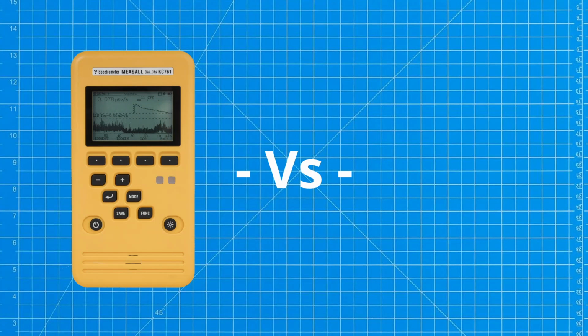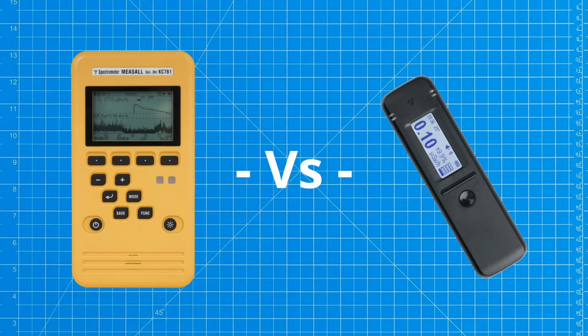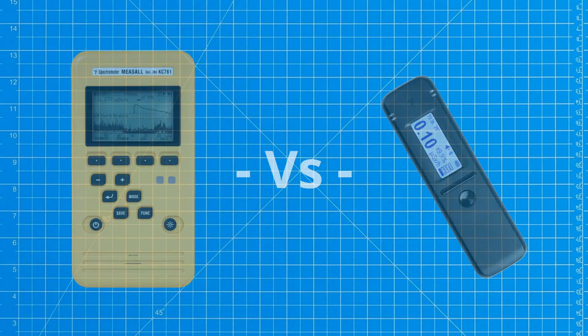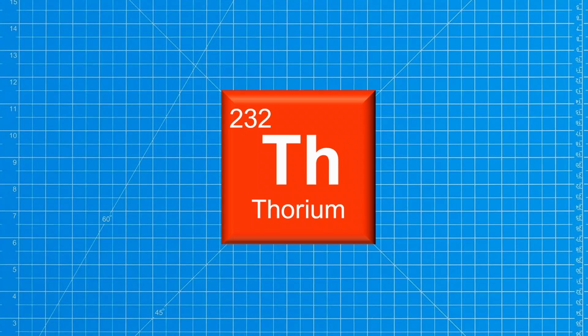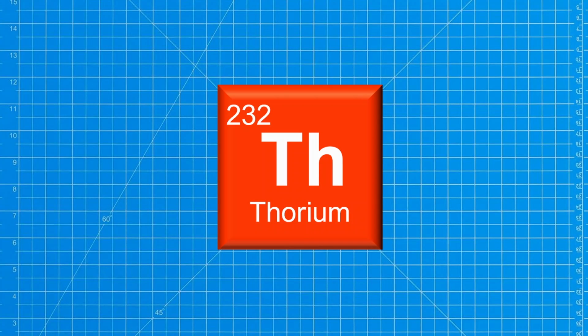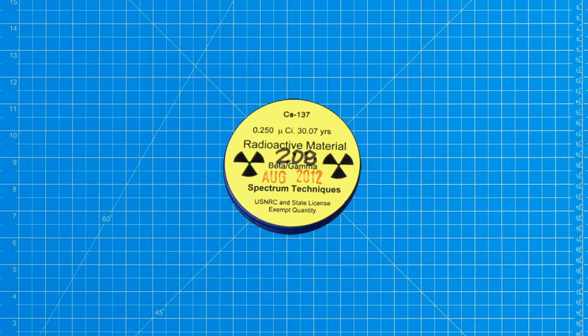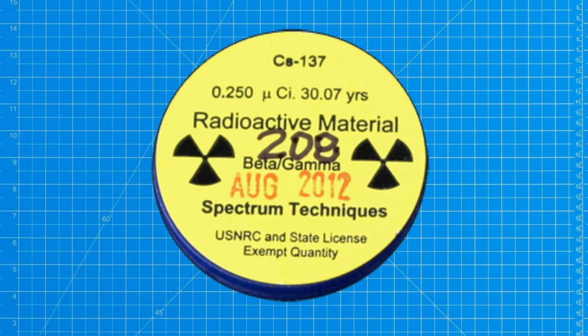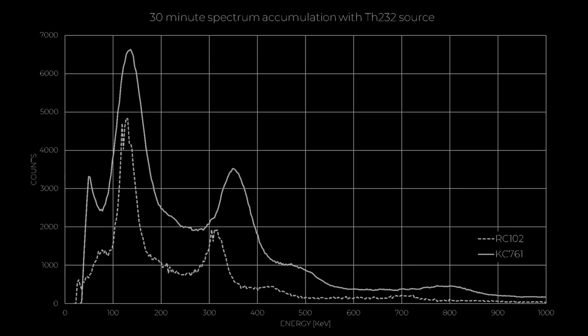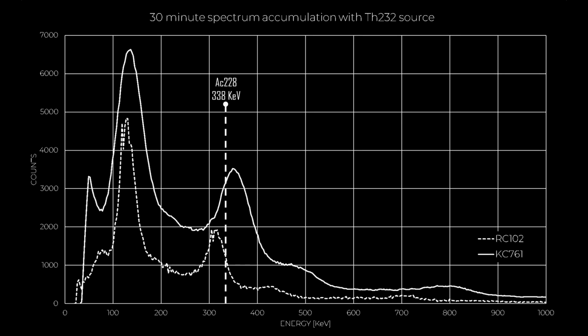So, how does this device compare to the RadiaCode 102 product in terms of spectral resolution, accuracy and sensitivity? I conducted an experiment using a thorium-232 source on both of these devices, to try and find out. Normally, this measurement will be conducted using a cesium-137 test source, but I don't have one of those, so I am going to need to make some assumptions and calculate some corrections to the data that I have collected.